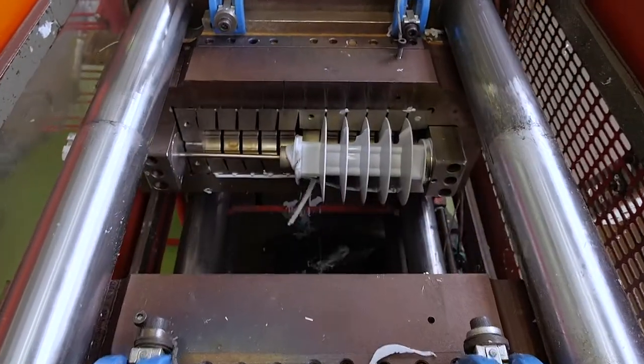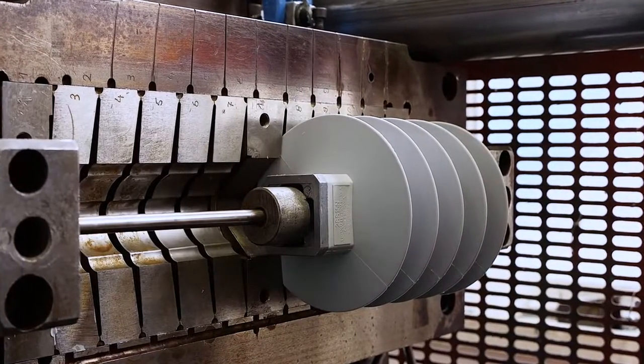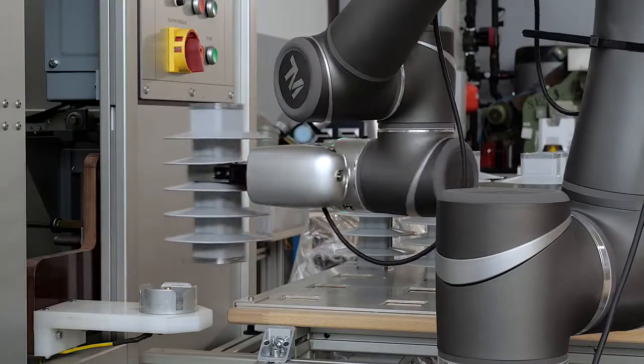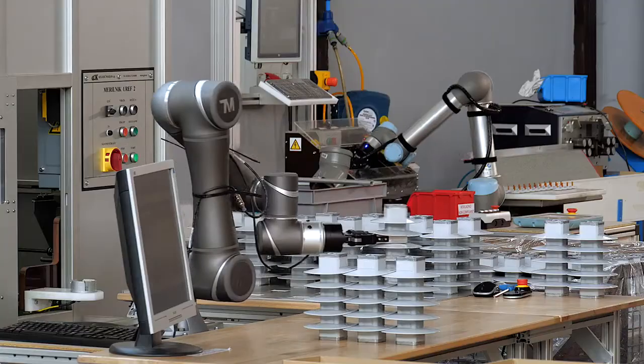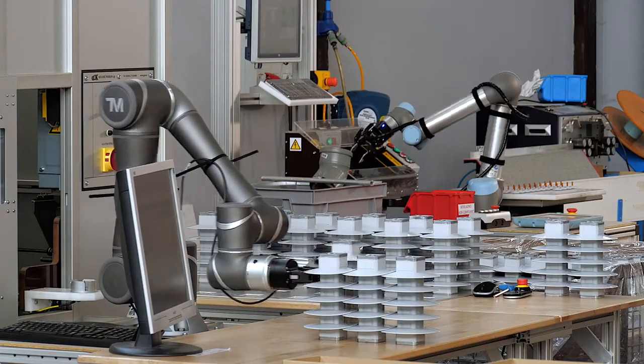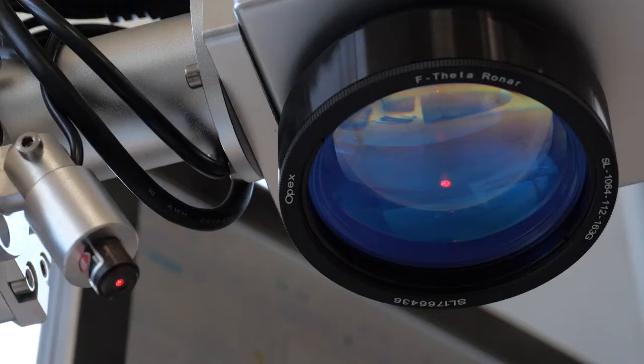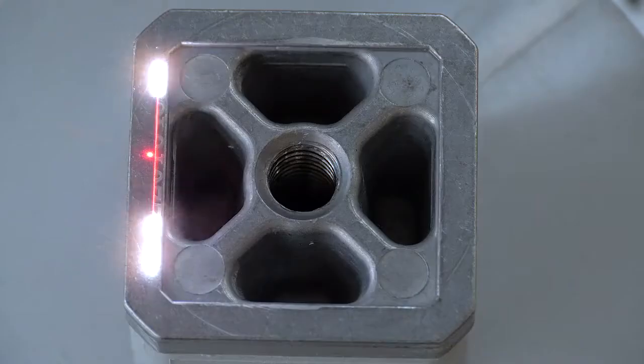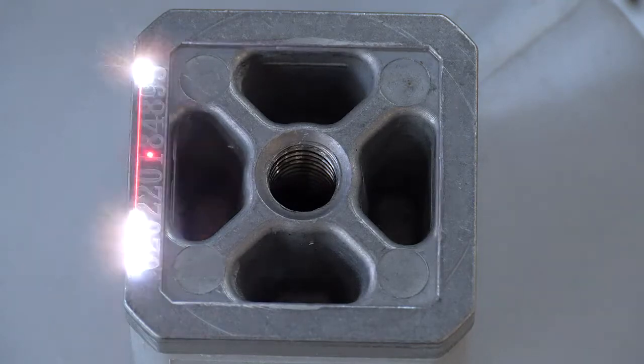After siliconizing, all surge arresters are 100% tested on calibrated devices where partial discharges, reference, and residual voltage values are measured using routine tests. The reference number of the conducted tests is then engraved onto each surge arrester.